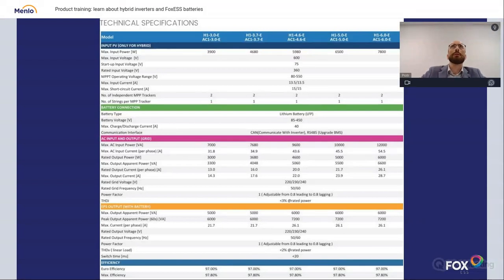Every such unit, H1, comes with two independent trackers, one string per tracker. Those trackers are independent, working like two different inverters. So you can even use a different brand of PV modules if you have them, remembering to put one brand on one tracker, the second brand on the second tracker. Those will operate as usual.